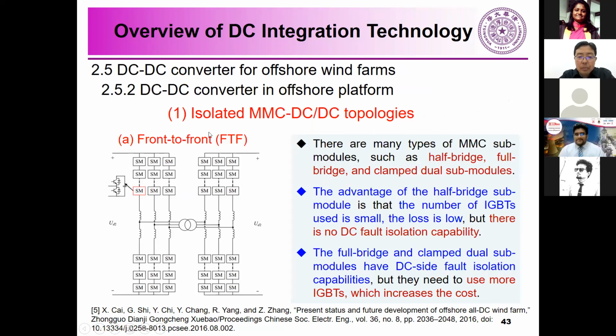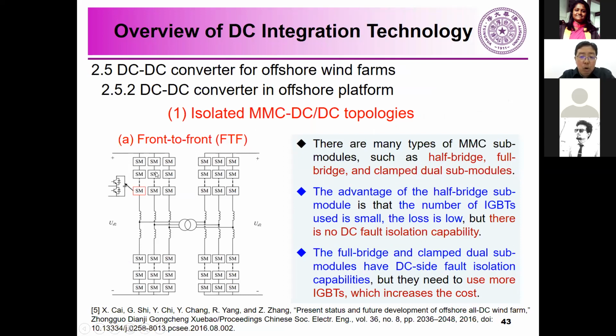And here it shows the isolated modular multilevel converter, the MMC-based DC-DC topologies. We can use half bridge, full bridge or clamped double submodules. The advantage of half bridge submodules is that the number of IGBTs is lower, so the power loss is low, but there is no DC fault isolation capability. If we use the full bridge and clamped double submodules, they have DC side fault isolation capabilities, but they use more IGBT devices, which increases the cost.